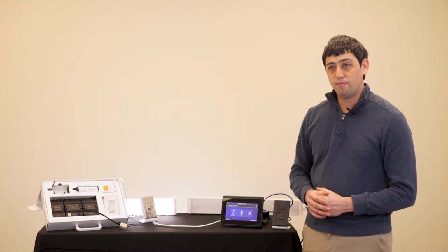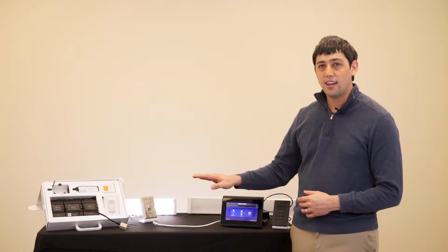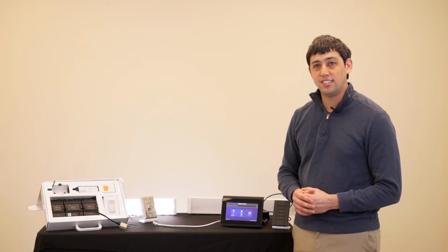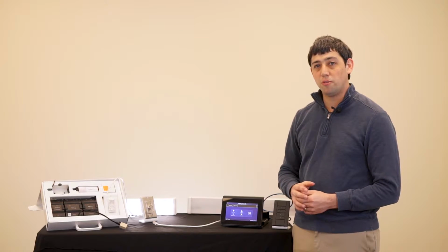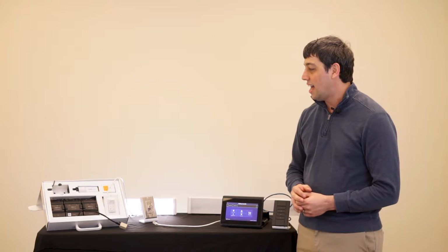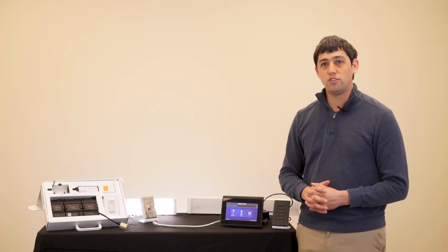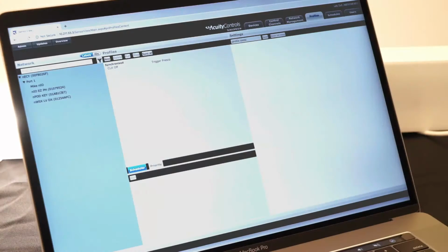nLight network. So with your nECY, you'll connect your bridges and all of the devices in the rooms as you would normally do for an installation. Then you'll go into SensorView, make sure to name all of your devices, and then create the profiles that you need containing those devices with or without a schedule, and again, depending on which system is your scheduling system.